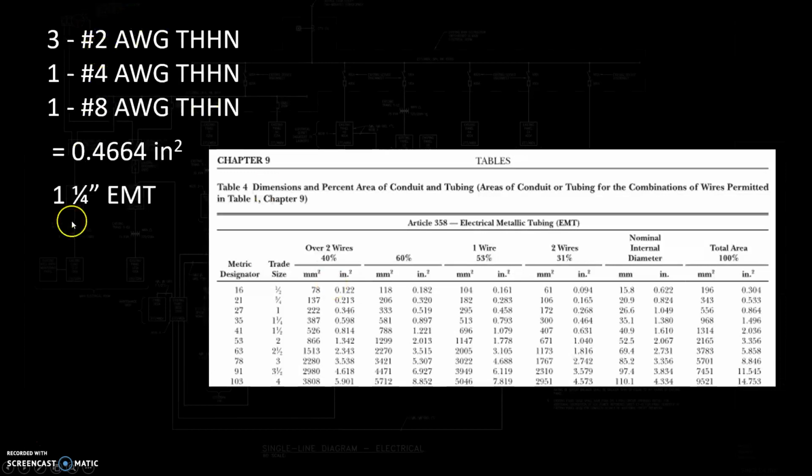Even this example in a 1 1/4 conduit, I'm thinking, gee, that's going to be really tight. So again, for any textbook examples, go with what the math says. But in the field, you may want to consider applying some common sense here and maybe increasing by a size if it seems appropriate. So anyway, conduit fill, make sure you guys are up to speed on that.